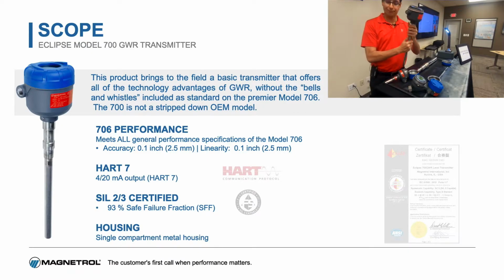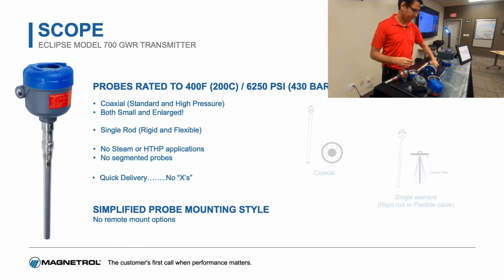That's right here. Waiting for this to come up next. Then the next way that we're getting cost out of it is we're limiting the permutations of probes that are available. And also the probe design is fixed, that we are only going to offer it in coaxial and in both a standard single rod and with a flexible cable. And by doing that, we're going to limit the choices of the permutations of the probe types, and the probe is fixed into the housing so that there's no expensive coupling between the probe and the housing.